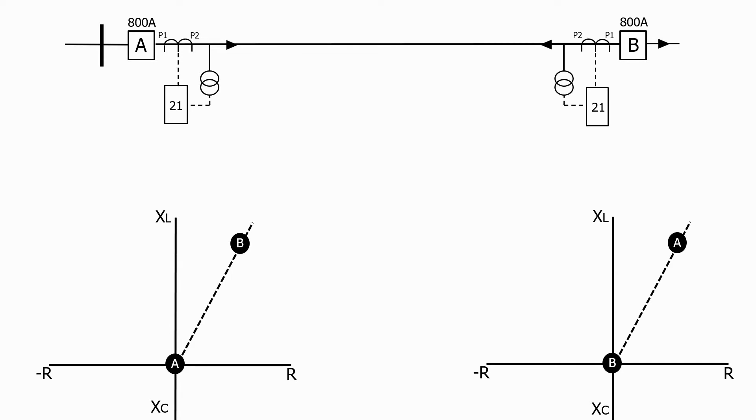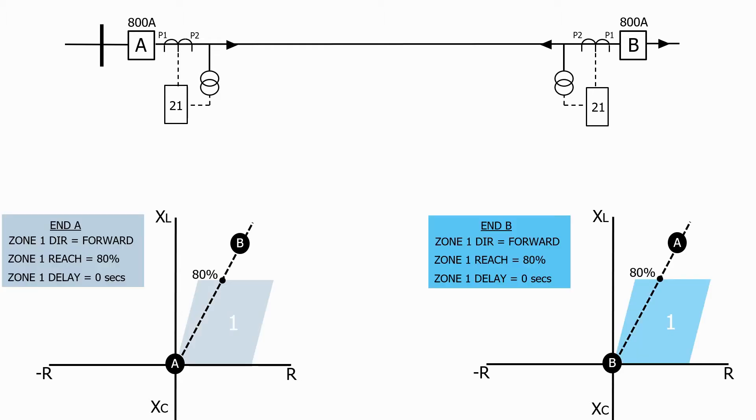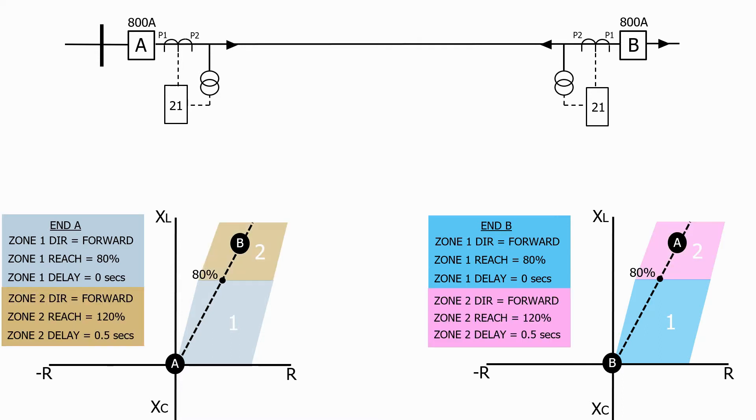Here we have our two ended feeder from before with an impedance relay on both ends. As before we set the zone 1 reach to 80% for both relays and made them instantaneous, and the zone 2 reach to 120% and given them a small time delay.